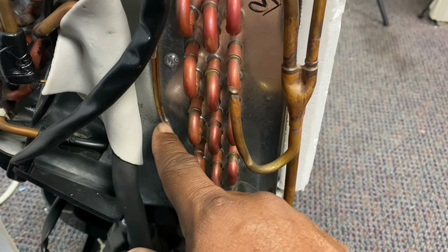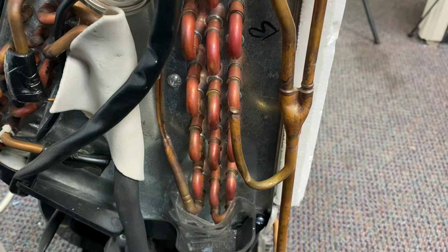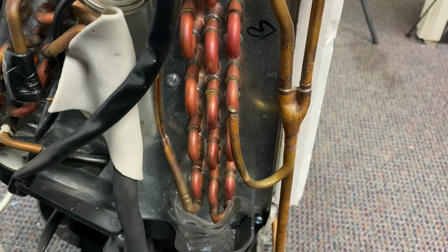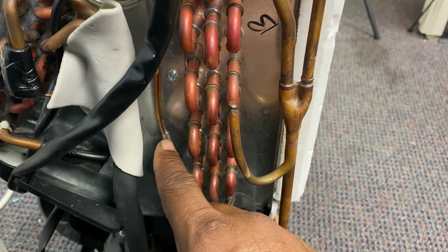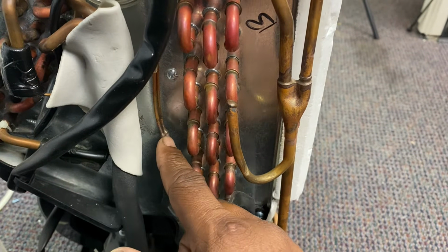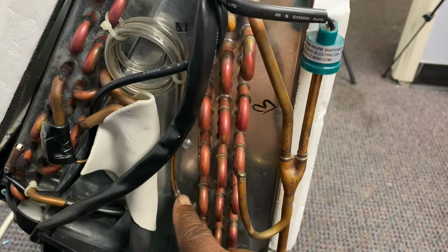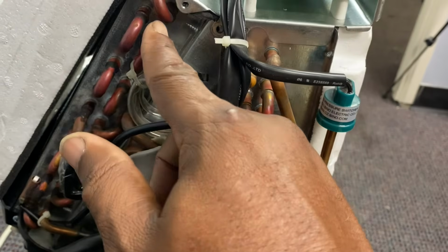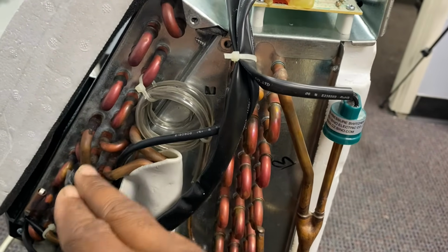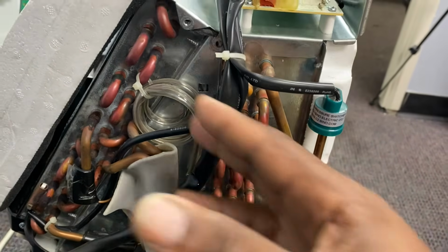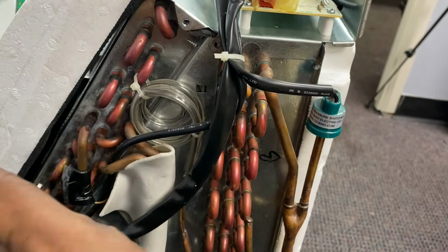This is called the expansion valve. It cools down the refrigerant. It depressurizes the refrigerant. It comes from a very pressurized hot state, and it gets depressurized right here at the expansion valve. See how this tube here is very narrow? That depressurizes the refrigerant, okay? And that depressurization causes the liquid refrigerant to become cooler, and it fills these coils here called the evaporator. And as the fan blows past these coils, it blows out cool air because the refrigerant is cooled off.